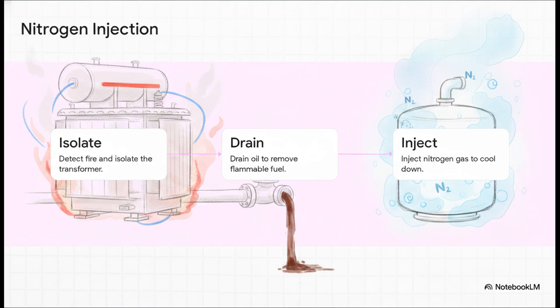This is where it gets really interesting. There's this unconventional but highly effective firefighting method that completely replaces traditional water sprinkler systems. Here's how it works. When a fire is detected, the system immediately isolates the transformer. Then a valve pops open to quickly drain the oil. It's literally pulling the fuel right out from under the fire. Finally, it continuously injects nitrogen gas into the bottom of the tank. This rapidly cools the whole system down, suffocates the flames, and absolutely prevents any reignition. It's basically a brilliant, completely self-contained rescue operation.